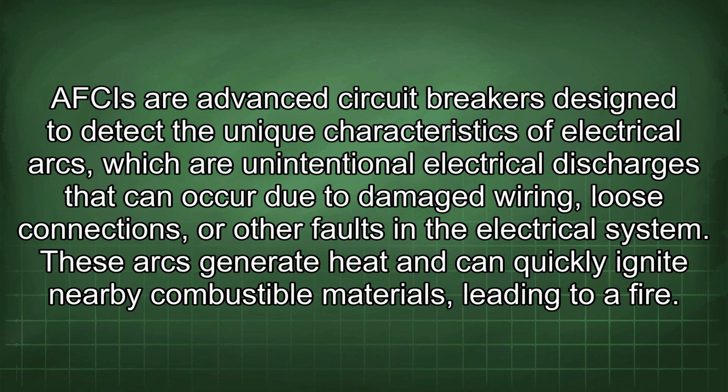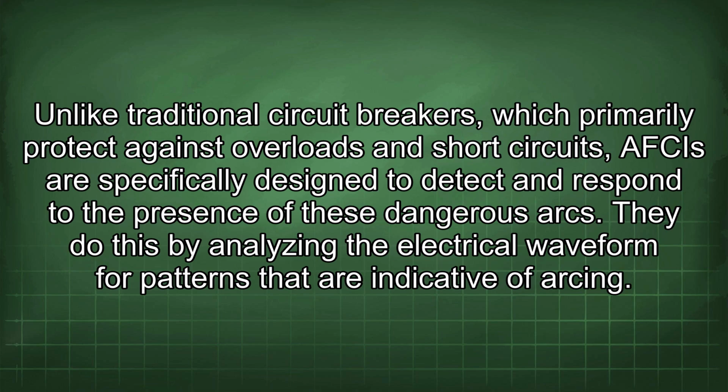AFCIs are advanced circuit breakers designed to detect the unique characteristics of electrical arcs, which are unintentional electrical discharges that can occur due to damaged wiring, loose connections, or other faults in the electrical system. These arcs generate heat and can quickly ignite nearby combustible materials, leading to a fire. Unlike traditional circuit breakers, which primarily protect against overloads and short circuits, AFCIs are specifically designed to detect and respond to the presence of these dangerous arcs.